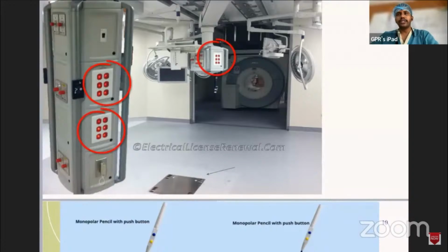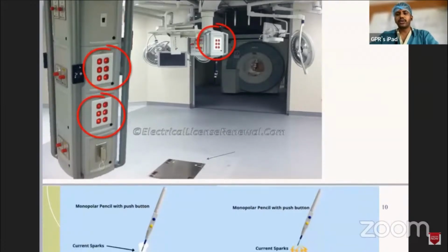So whenever we see an operation theater, the center of the operation table will have this particular circuit, not just to fix the table in situ, but also to have the conductive tile next to it, to make sure the conduction or the grounding is happening.